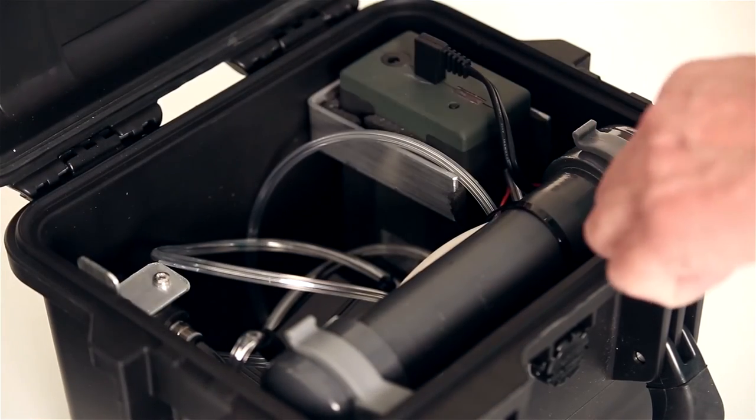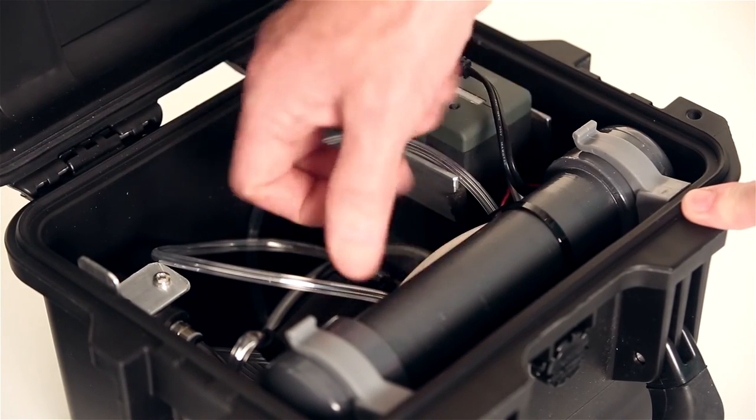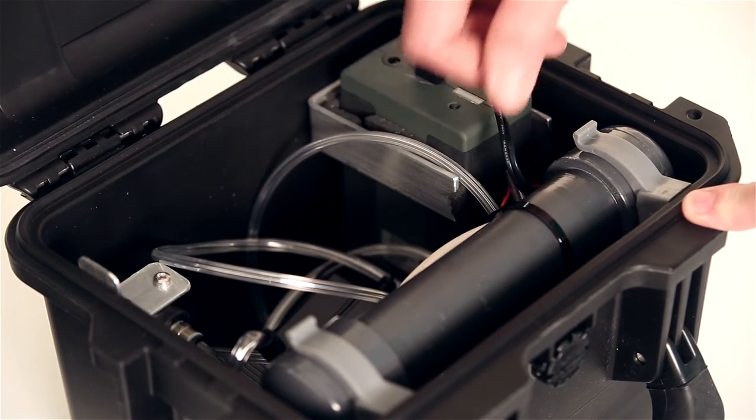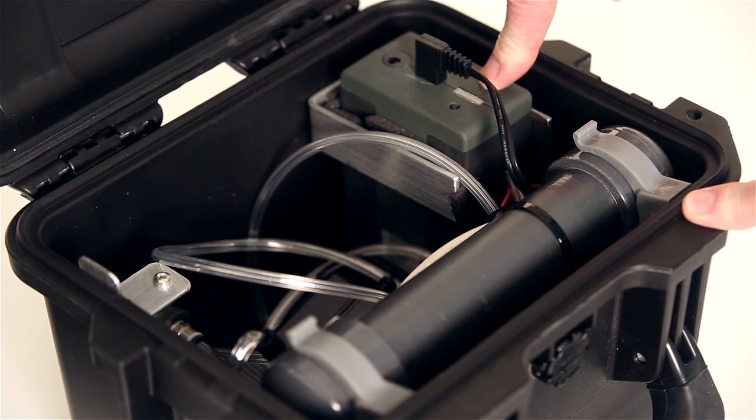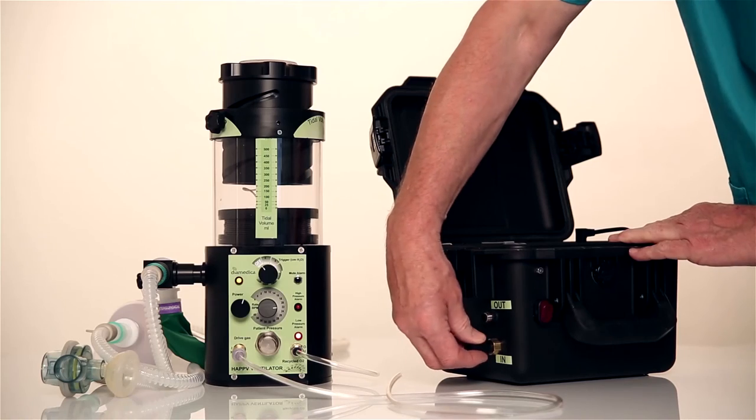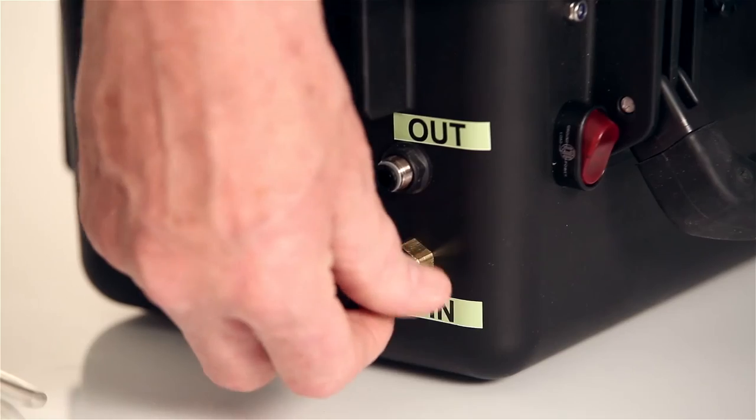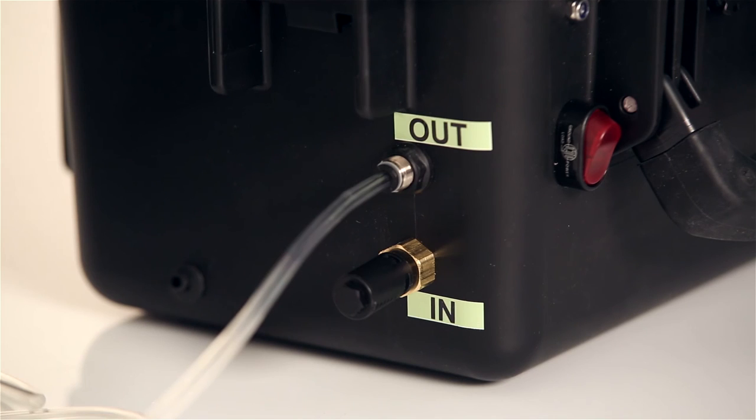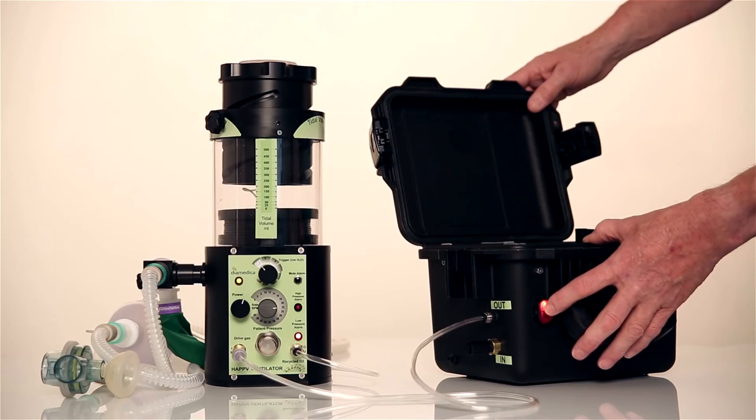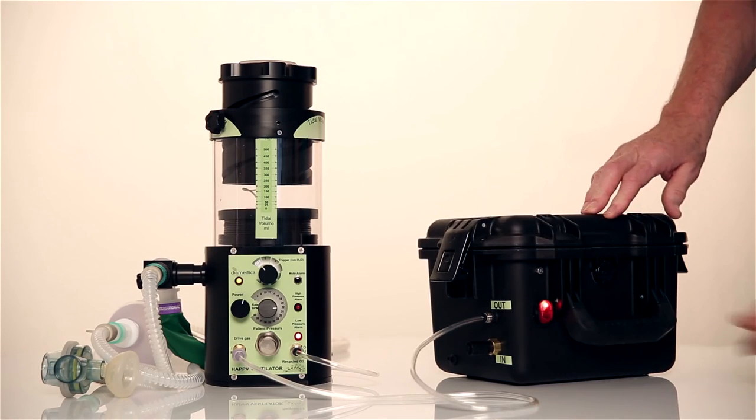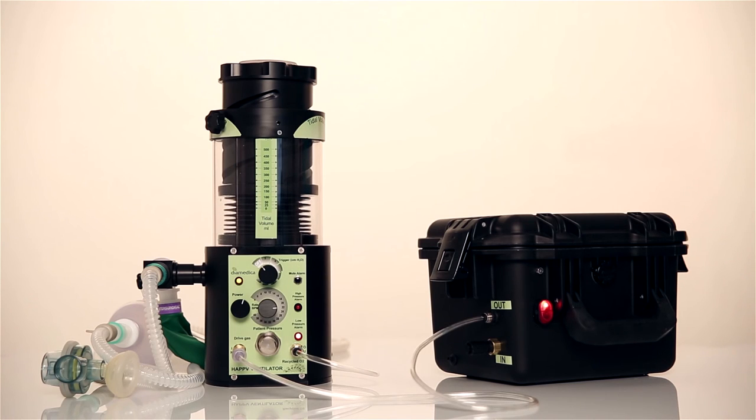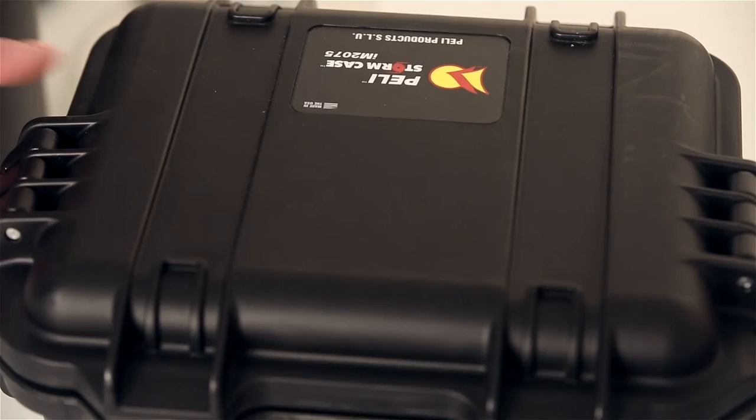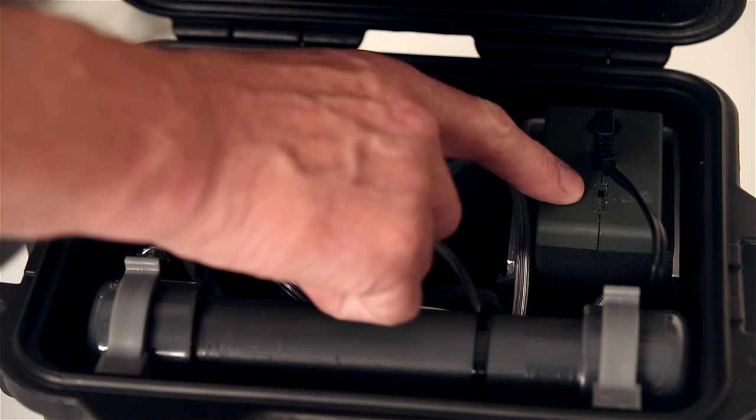The compressor pump contains a pump, small reservoir, lithium rechargeable battery, and water trap. The inlet filter is first screwed into place and a drive gas tube connected between the pump and the ventilator. The pump is then switched on. The battery should run for 20 hours when fully charged. The level of charge is shown here.